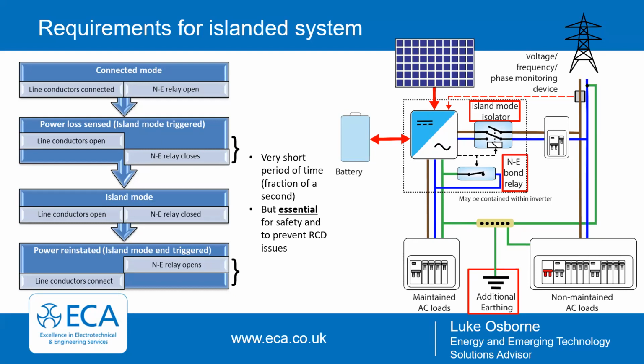On the left-hand side of the screen, you can see how the island mode isolator and the neutral bond relay operate. When the system is connected and the grid is live, you've got the line conductors connected, but the neutral earth relay is open. When there's a power loss, the line conductor relay opens and the neutral earth relay closes to make sure you've got that safety in place. The reverse happens when the grid power is restored.